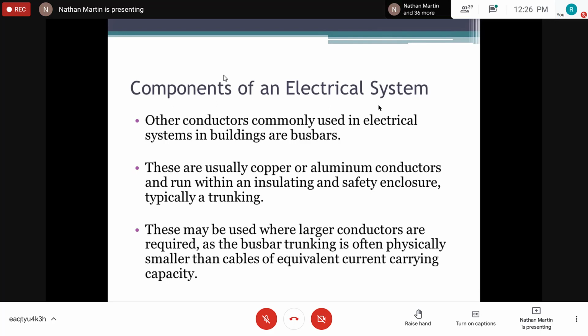No, the thing about the bus bar trunking is that when tightening your lugs and so forth onto them, right? And when tightening those cables onto them, you use a lug and not a bolt. Now, one thing you need to understand is the torque requirement of these bus bars, because of the high current we expect them to carry. You have to ensure that these cables are affixed properly. If you want to see what one looks like, when you go to the power lab today, entering the power lab to your right, there's a bus bar trunk in there that you can actually view and see how they make the connections to the bus bar, right?